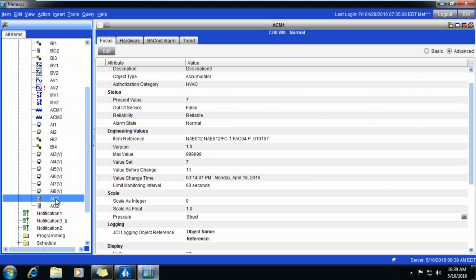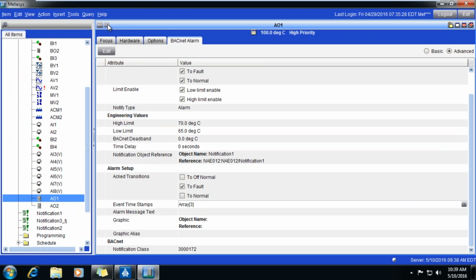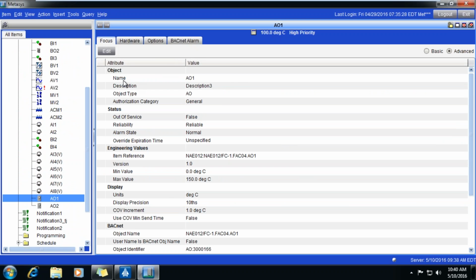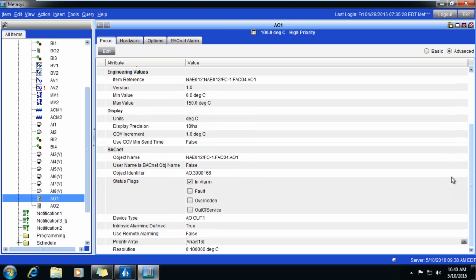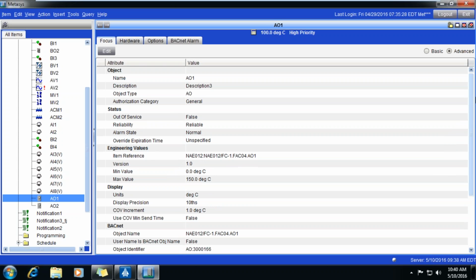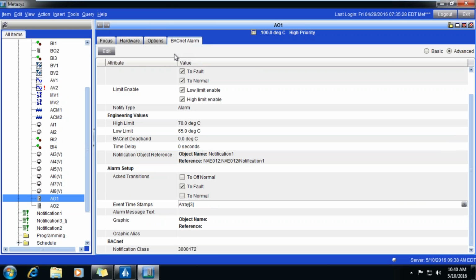So the other thing that Glenn spoke about that's new in this release is things like supporting alarming, intrinsic alarming, which is if you have an object here like an analog output, so this just gives us an analog output of temperature, I can actually set up a BACnet alarm intrinsic to this object, and I can set an alarm that says, okay, notify me if this value goes to fault, and then notify me if it goes back to normal, and then I can enable low limits and high limits. So this is something new that these intrinsic alarms are now supporting.